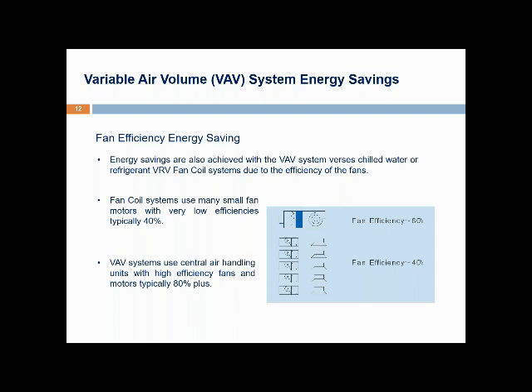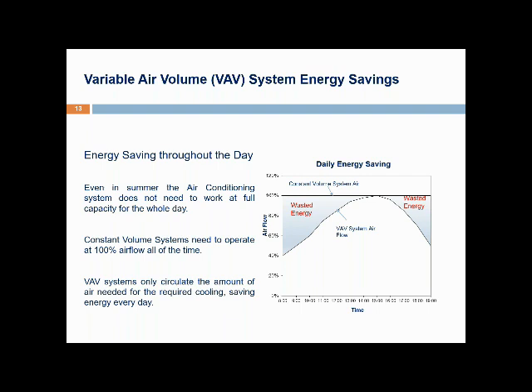Comparing VAV systems to fan coil systems — chilled water or VRF — the efficiency of small recirculation fans used with fan coil systems is very low, typically only about 40%. The efficiency of air handling unit fans and motors is typically around 80% or more, a big difference. Also, with fan coil systems the airflow is there whether it's needed or not, using more energy. VAV systems save energy throughout the day, every day. During non-peak cooling hours, the system only provides the amount of cooling needed to meet the actual load, avoiding wasting any energy.